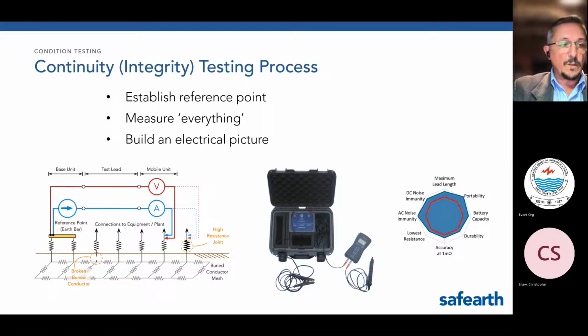In fact, we tend to see around the world that earthing specialists are saying any type of disconnection is more dangerous than the benefit you get from measuring with that disconnection. So all of your testing methods should be aimed at being able to effectively measure with everything intact, in place, and not disconnected. So let's have a look at an example of the continuity testing process. We establish a reference, we walk around with a probe and a meter, and we measure everything in the yard, trying to build an electrical picture to try and see even small changes in milliohms can indicate there's a problem.